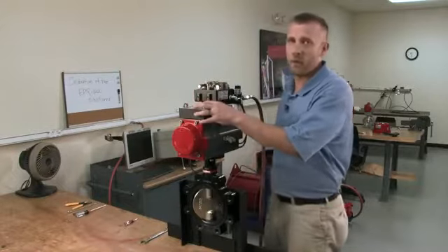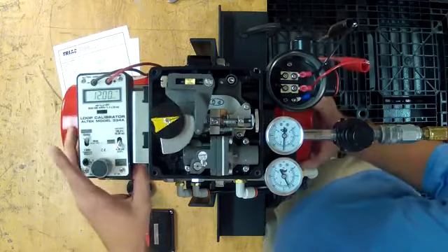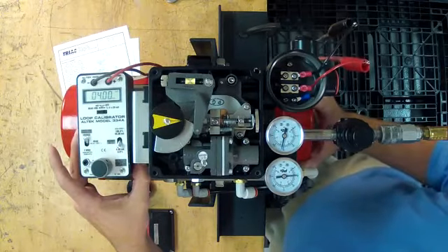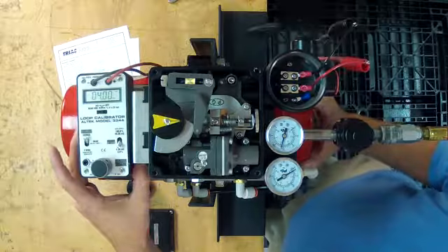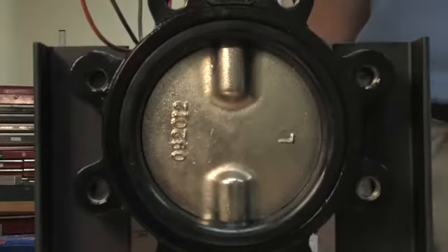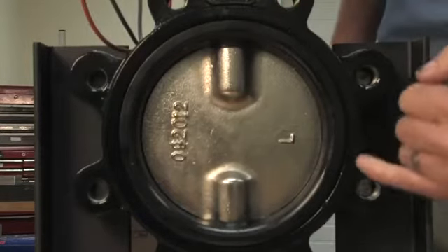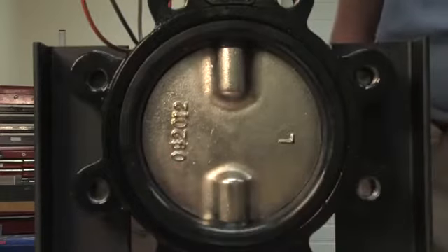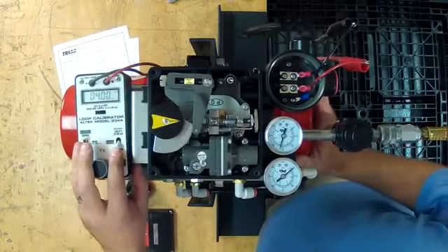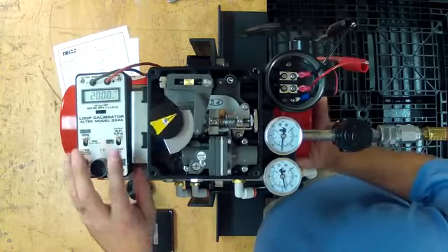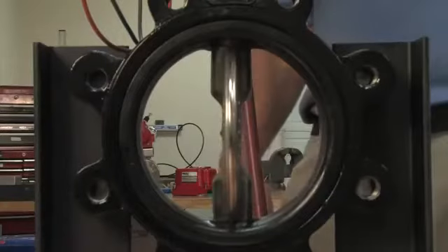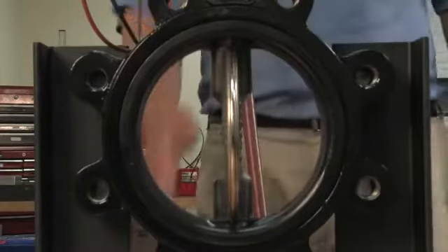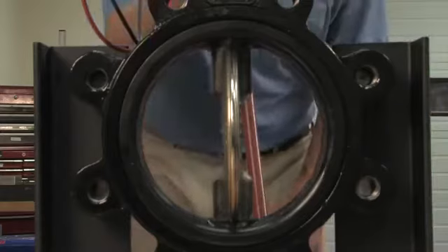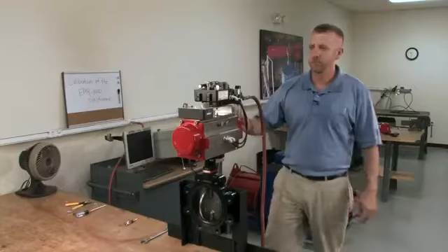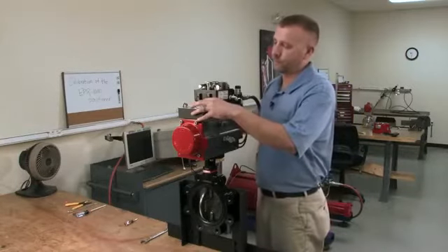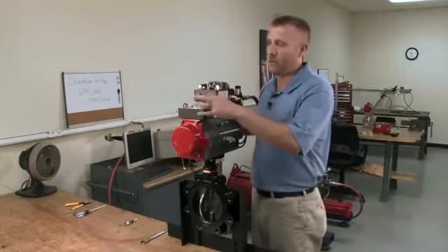So now we're going back down to 4 milliamps. And you're looking for a nice even seat in your valve, which we have here. A nice even distance on this side to this side. Back to 20 milliamps, and you want a nice straight through, parallel to the actuator flow pattern. Okay, we're going to go back down to 4 milliamps.